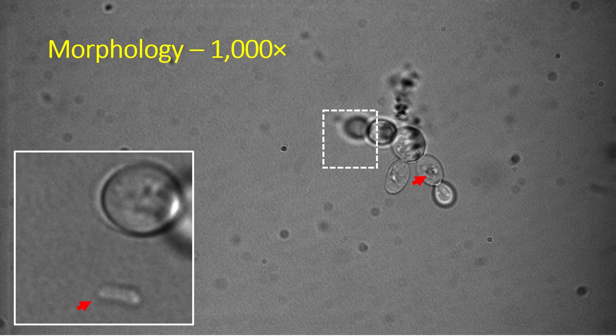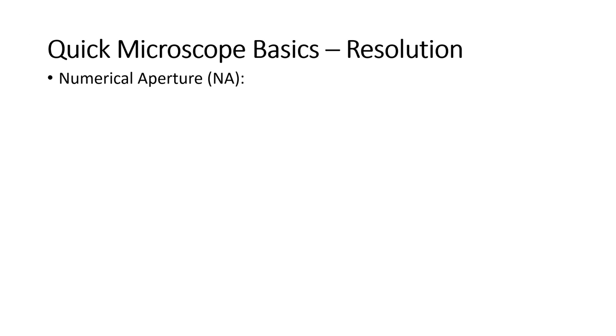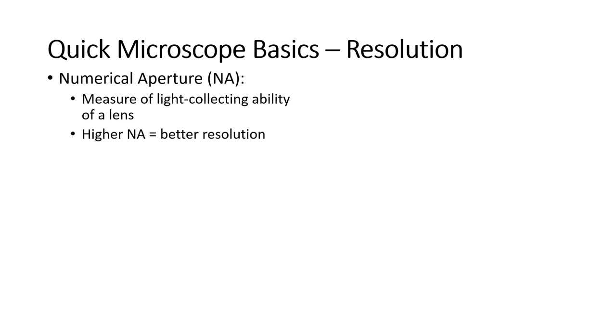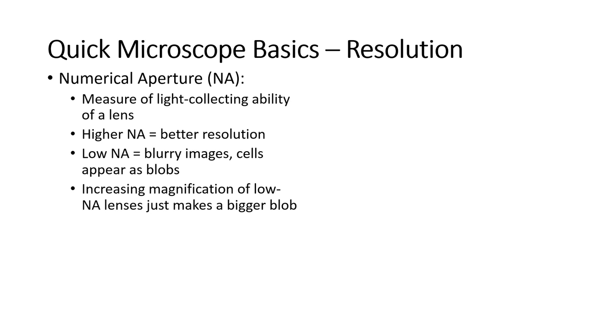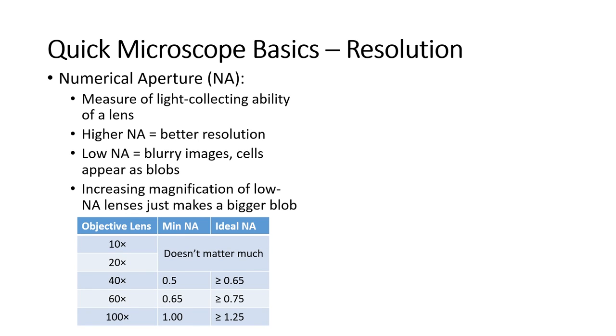Magnification isn't the only thing we need to worry about when selecting lenses. There's one rather important aspect to consider, and that's the resolution of the lens, determined by something called the numerical aperture — this is in addition to the magnification. Basically, the numerical aperture is a measure of the light-collecting ability of a lens. The higher the numerical aperture, the better the resolution. If we have a low numerical aperture lens, it will produce an image of a cell that's somewhat blurry — cells may just look like blobs. If we increase the magnification but keep the numerical aperture the same, the cells just get bigger but still look like blobs. You just have a bigger, blurrier image without additional detail or structure.